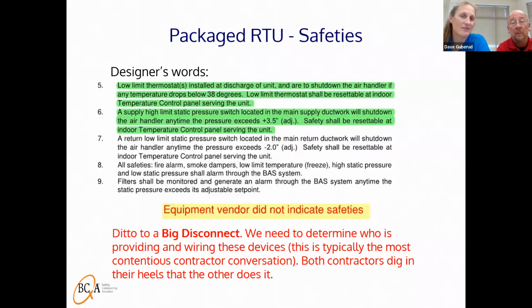Here, this goes back to the safeties that Dave touched on in that schematic page. The designer's words indicated that low limit and supply high static would shut down the unit, and that those safeties would be resettable at the indoor temperature control panel in the unit. The equipment vendor did not indicate safeties, and nor did the control contractor. So it's really determining who's providing and wiring these devices. In this case, both contractors dug in their heels, saying it's the other person's responsibility. It's better to find this out at a controls page turn than at the end of the project.